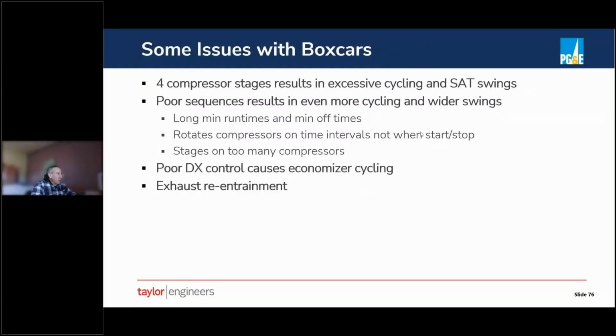In practice, we came across a bunch of operational issues in this data center and a similar one with this kind of concept. The box cars, which are packaged products used on hundreds, thousands of buildings of different types, don't always work very smoothly. These ones had 4 compressor stages that resulted in pretty significant cycling and temperature swings. To make it even worse, the internal sequences that came with the units didn't make a whole lot of sense, which resulted in even more cycling and swinging. They had a long minimum runtime, so the compressor would come on, overcool, keep running and overcooling even more, and then it would have a long minimum off time. So then the temperature would get higher.